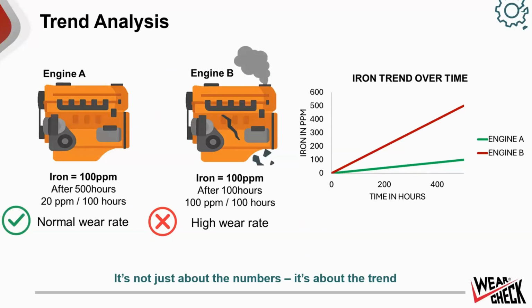Now, it's important to understand that the absolute wear values that the laboratory gives us are not entirely relevant. What is meaningful is how the number has changed from the last oil sample. So we are not just looking at the amount of iron, but the amount of iron for a given time period. We are looking at a wear rate, not a static wear value, because wear is a function of time. And that is why we use trend analysis.